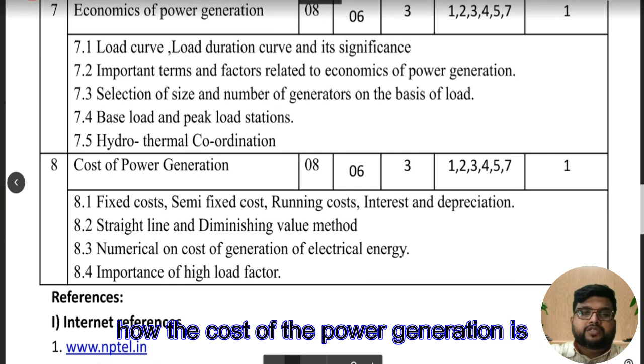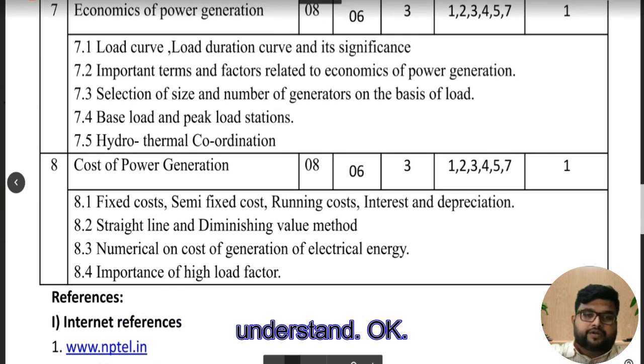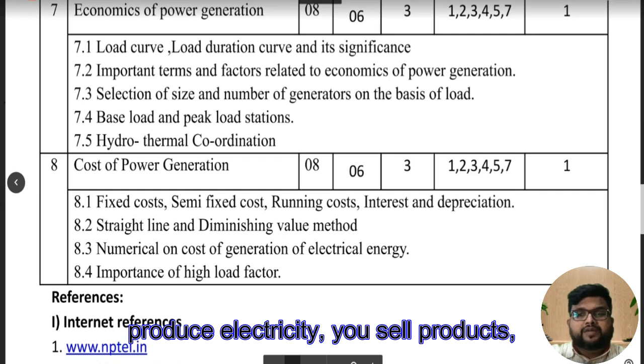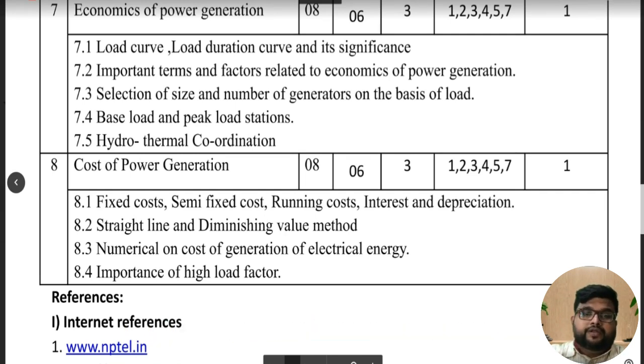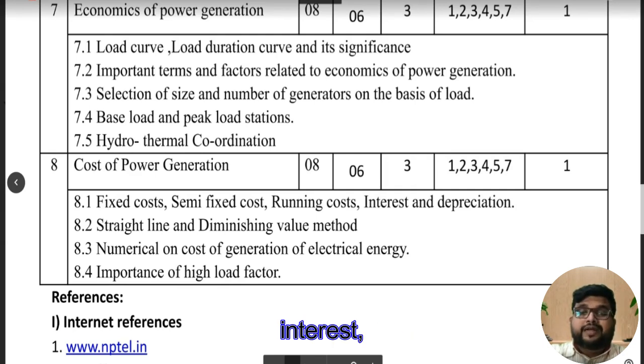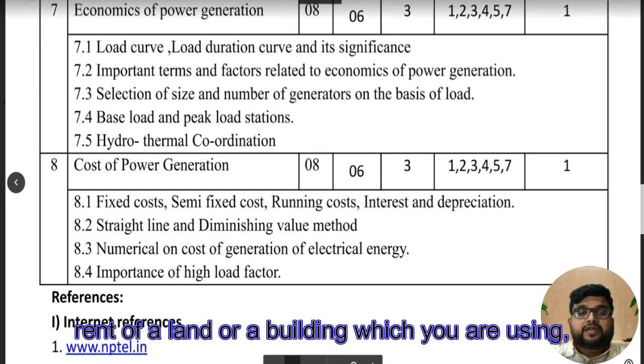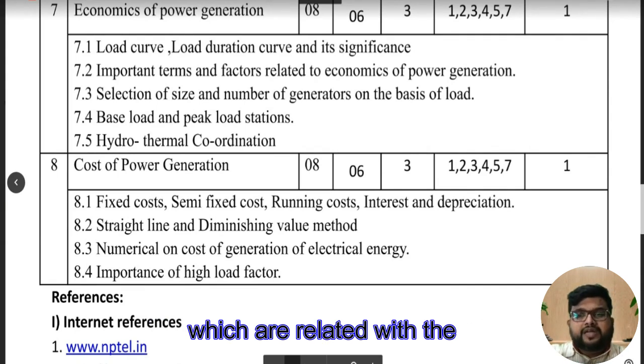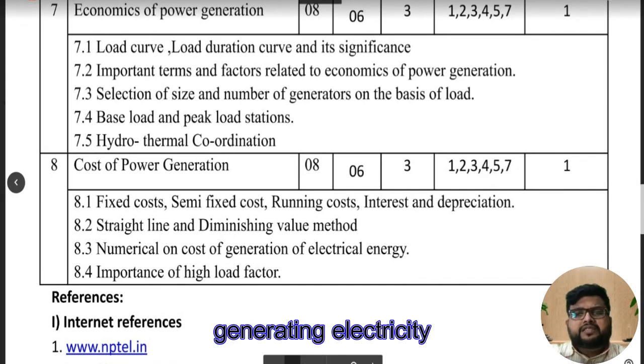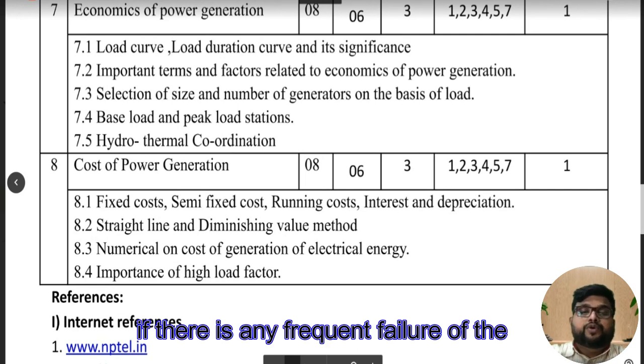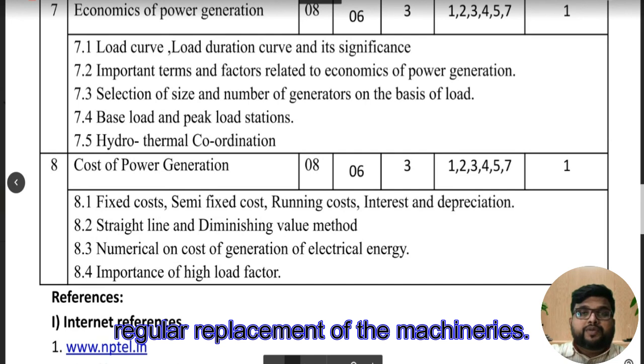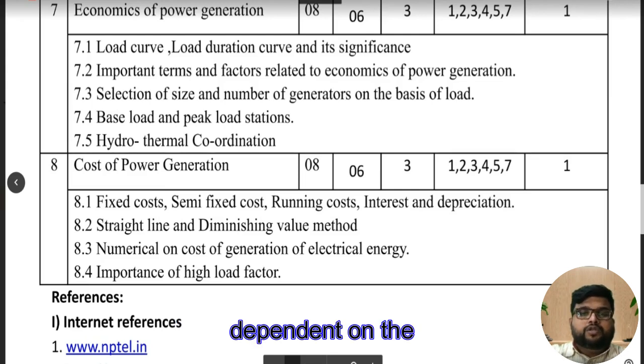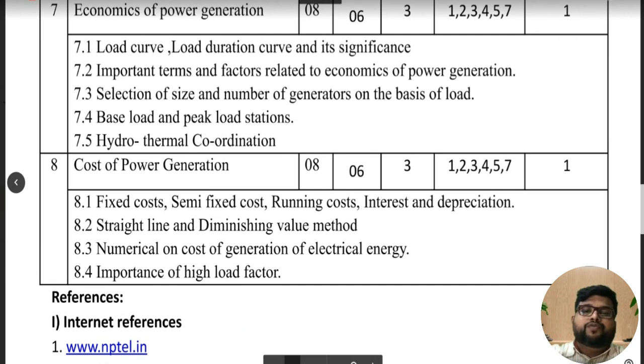In this economics of power generation chapter, we need to understand how the cost of power generation is calculated. Fixed cost is like whether you produce electricity or not, whether you sell it or not, you still need to pay — that includes salary, maintenance, insurance, interest, depreciation, property tax, and rent of land or buildings. Semi-fixed costs are related to events like frequent machine failure or the cost of regular replacement of machinery.